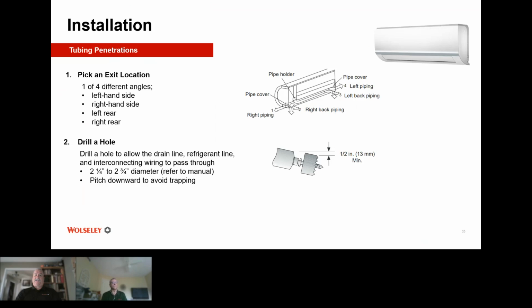Now, when you are making the hole, one thing that I have noticed in my experience is do not make the hole go straight through the wall. Give it a little bit of an angle down. Half an inch should suffice. What that does is help if you are using just the condensate to flow out the back, or to flow into, let's say, a hard pipe inside a wall. You just want to maintain a positive slope down or away from the unit, so that gravity will do its job and take the condensate away from the indoor head unit.